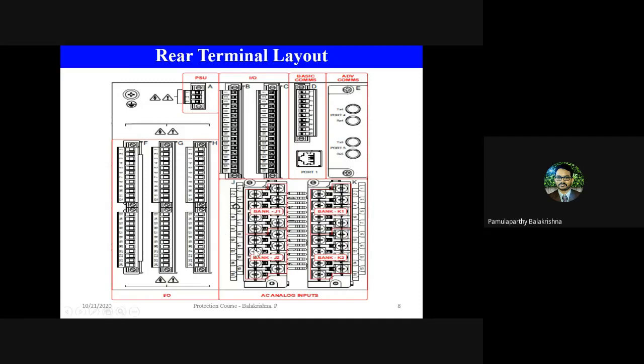One more advantage with this is, in earlier days, if one particular signal was not working properly, you had to replace the entire relay box. But here you just replace this bank, just lift it out and connect it. Even the connection is hot swappable, as easy as disconnecting the charging cable from your mobile and keeping it back. So it is flexibly and modularly designed.